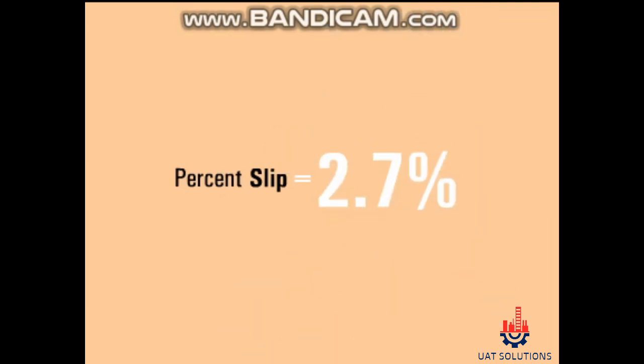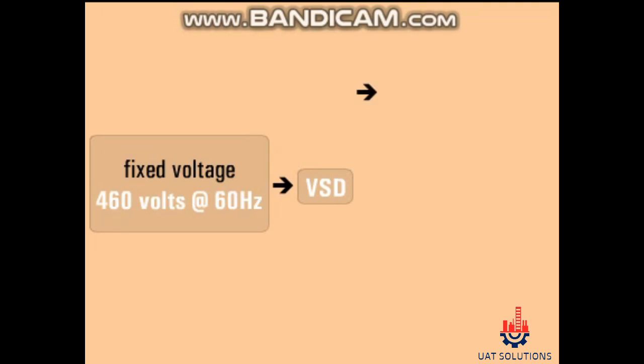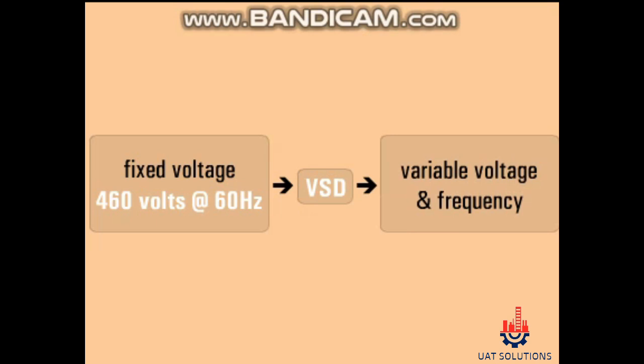The slip is not affected by the design of the VSD. With this information, we can now determine the correct voltage to frequency ratio for a particular motor. The variable speed drive accepts a fixed voltage and frequency of 460 volts AC at 60 hertz and supplies a variable voltage and frequency to the motor.